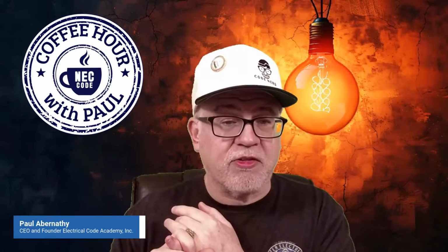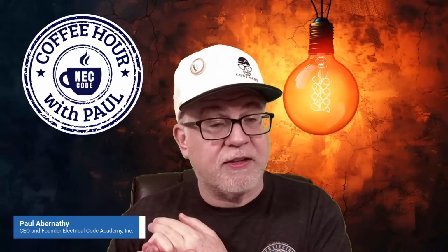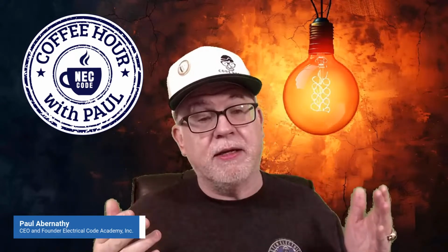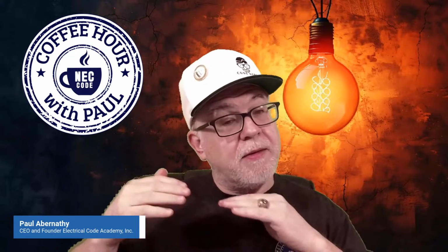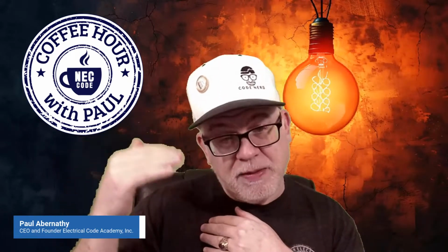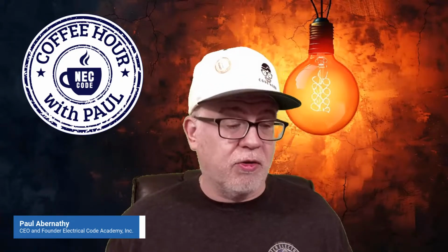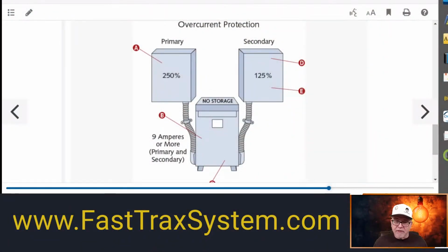And as long as those secondary conductors are sized properly, and as long as they terminate in, let's say, you follow the secondary conductor rules, you can do it. So remember, those are maximum rules. You don't have to be at the maximum. So most engineers will say, in this scenario, on this transformer, very rarely do they ever use 250% on the primary. Usually what the engineer will do is 125% primary, which also takes into account any loads that may be continuous that they're not aware of, and for the conductor sizing. So they'll do the primary at 125%. They don't go all the way up to 250. They do it at 125%, and they size the conductors at 125%.